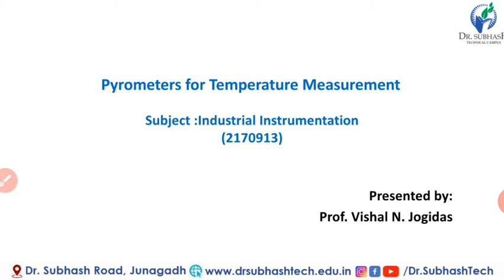Before starting, we must know the principle of pyrometer. What is a pyrometer? It is a device used for measurement of temperature without contact. For example, we have seen the resistance temperature detector, thermocouple, and thermistor. These transducers are also used for temperature measurement, but they should be mounted on the hot body or the temperature to be measured. It means if we have to measure the temperature of any body, we have to mount the thermocouple to that body, in contact with the hot body. Then we can measure the temperature of that body. So these transducers are known as contact type transducers, but pyrometer is different.